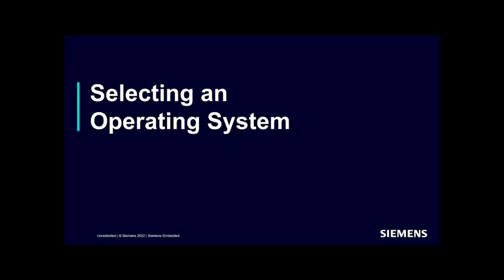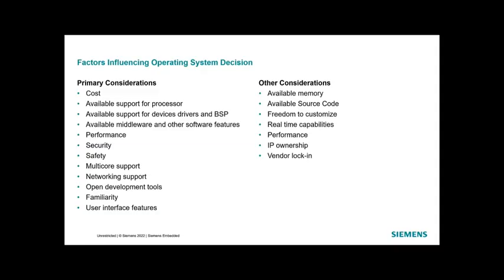How do you come to the decision to use an operating system in a medical device? It's similar to the decision in any embedded device, but more important to consider because of the regulatory approval required. There are many considerations — for example, if I'm making an MRI scanner, RAM and ROM size might not really matter, whereas for a very small device it may be a huge consideration. So it's all in context. Will my design fit? Many people when they think of Linux think of a desktop with eight gigabytes of RAM or more, but no embedded medical device is going to look like that — you want small devices with a small BOM cost.